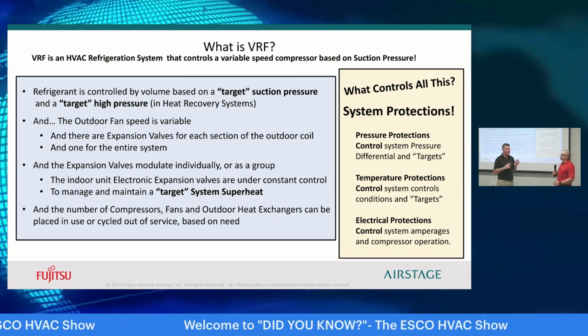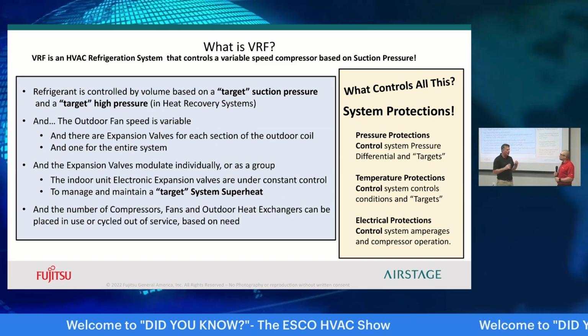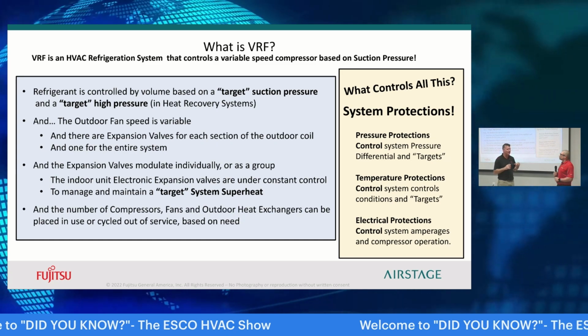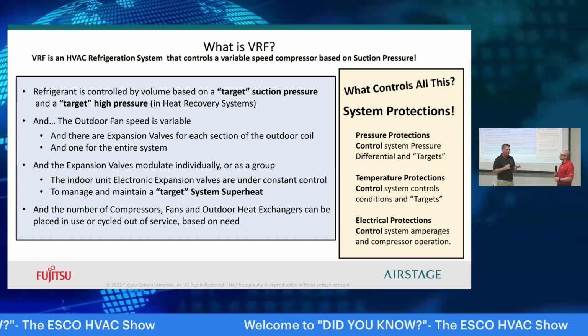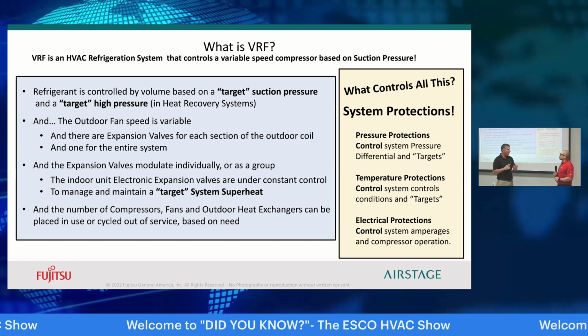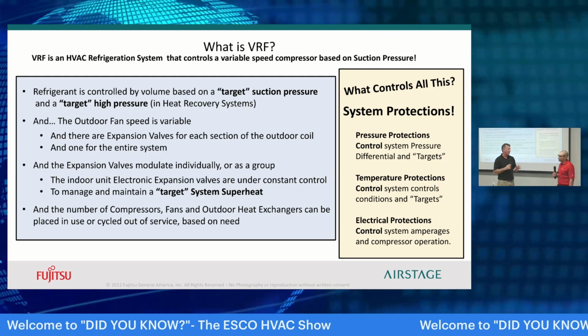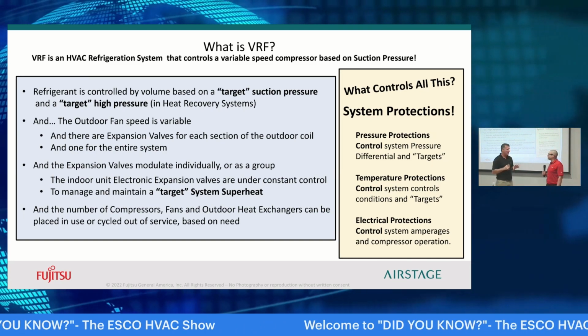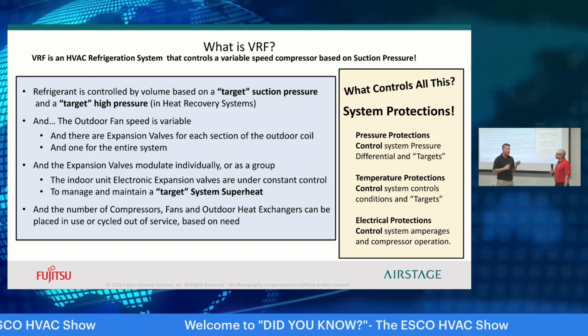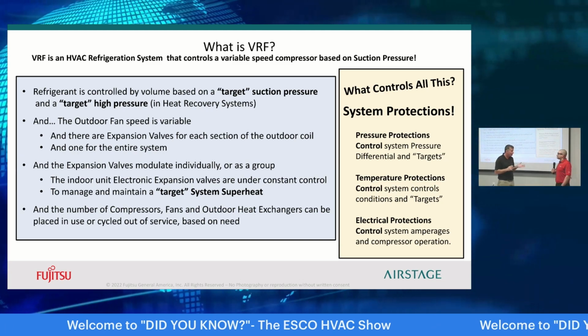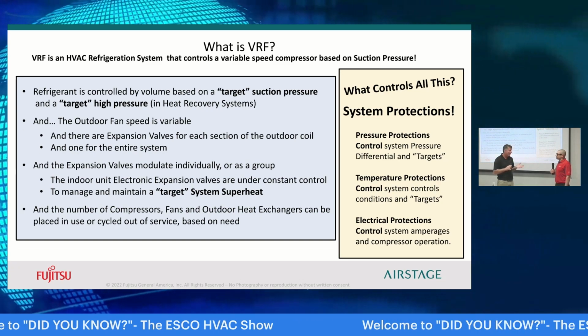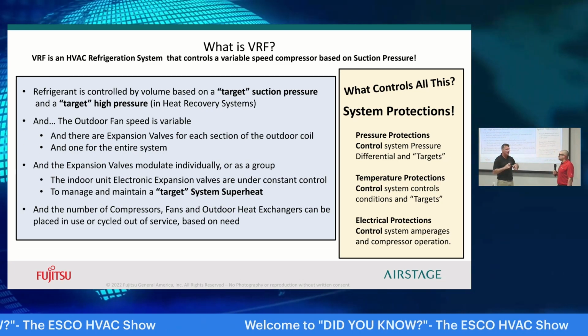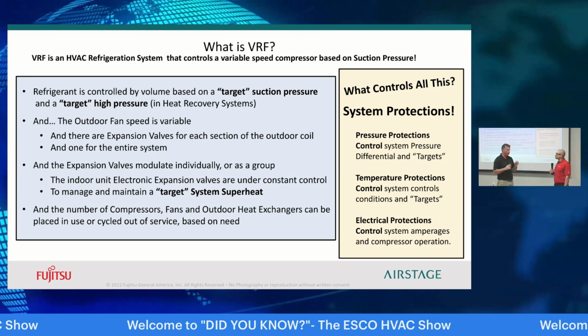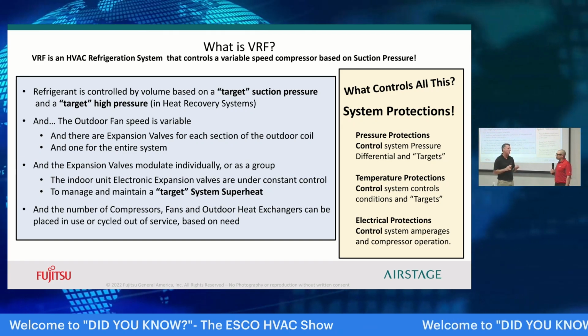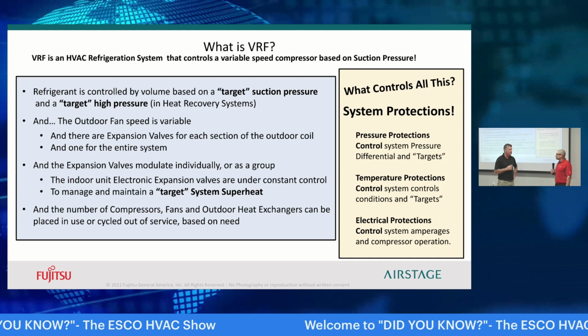That's one of the things I really took from this class, kind of retraining our old mentality of, okay, if I'm going to conserve energy, why don't I just give it a big setback, or why don't I just shut this off? That's really not the case with VRF, because some of these pieces of equipment can run down to like 15, 20, 25% capacity, very, very low capacity. So we get longer run cycles with extremely low operating current in amps. And that's really the biggest thing.